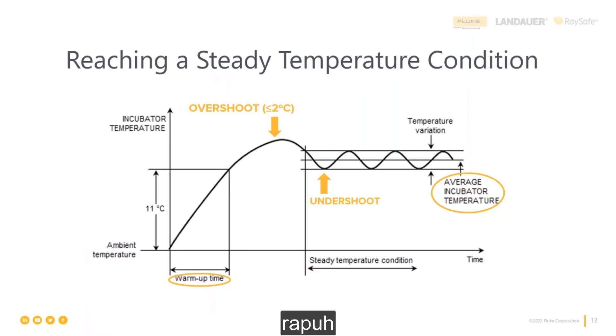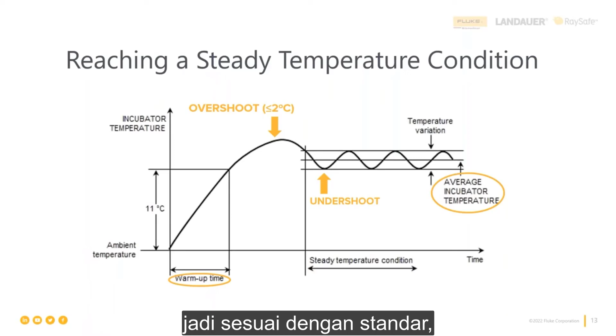So when we think about the acceptable ranges that an incubator overshoots or undershoots, as pointed out in the little diagram here, we must remember how fragile the infants are that go into the incubator. According to the standards, for example, the IEC 60601-2-19, and we will discuss standards in greater detail in just a few moments, that particular standard for incubator testing suggests that the overshoot should not be more than 2 degrees Celsius, which may not seem like a lot, but please remember again how sensitive and fragile those premature and sick infants are. So no more than 2 degrees Celsius over the set temperature as an overshoot is what is acceptable.